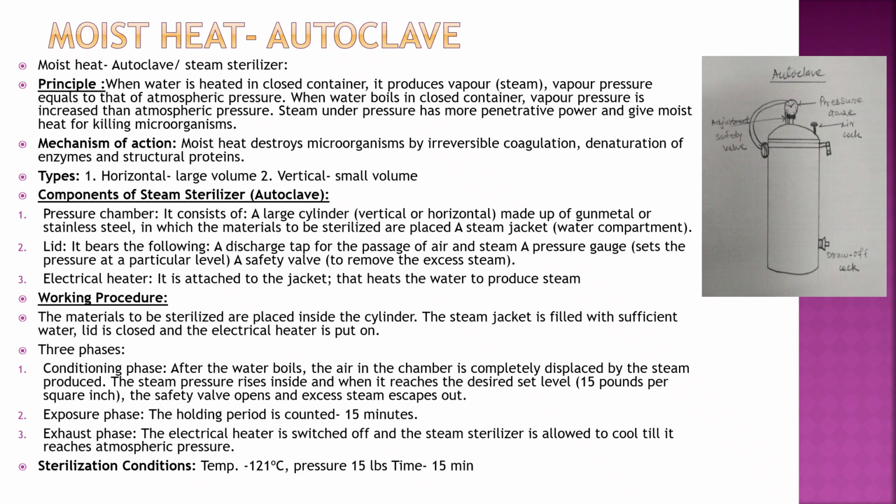Exposure phase: the holding period is for 15 minutes. Exhaust phase: after the holding period is over, the electrical heater is switched off and the steam sterilizer is allowed to cool till it reaches the atmospheric pressure, and then the material inside is removed.